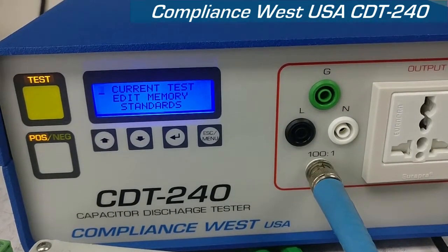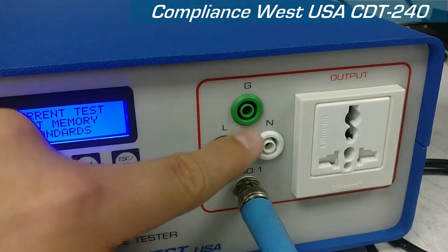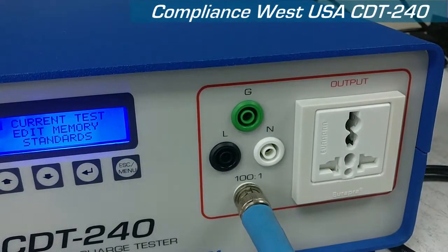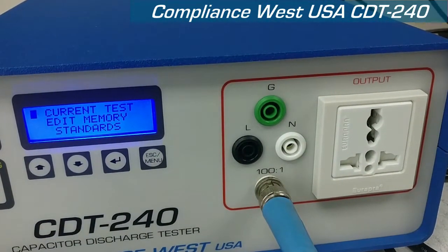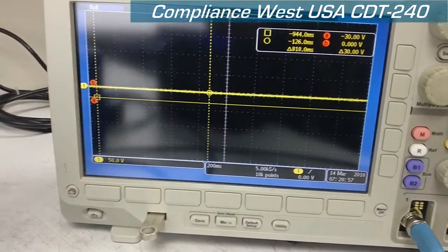The capacitor discharge tester has multiple outputs on the front. You have three receptacles for line, neutral, and ground. You have one universal output where you can use any kind of plug-in. You also have a 100:1 BNC connector that you can use to connect to an oscilloscope just for reference.